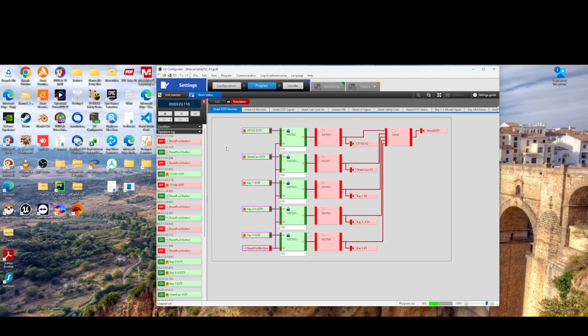I think there's a lot of code that gets repeated when it's not necessary because we already have this code that locks us out on an e-stop. In other sections of code farther through this, you'll find that this is repeated again. The resets are repeated and so forth. And it's really not necessary. Once it's been done, it's finished. It's complete. So I just wanted to let you guys know that what I did was recreate their code using this new PLC.